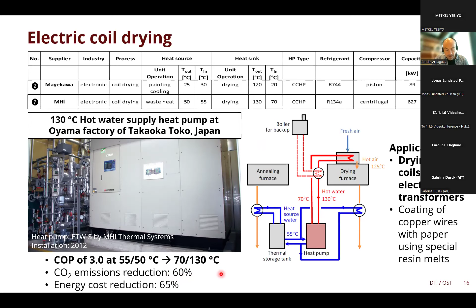The heat source is waste heat from the annealing furnace, and this is upgraded, also using thermal storage, to the 130 degrees. The COP is around 3. And compared to the steam boiler, CO2 emissions and energy costs could be reduced by 60 and 65%. The special learning here is that a detailed energy analysis of the heat demands and of the waste heat before the installation of the heat pump was key for the success.